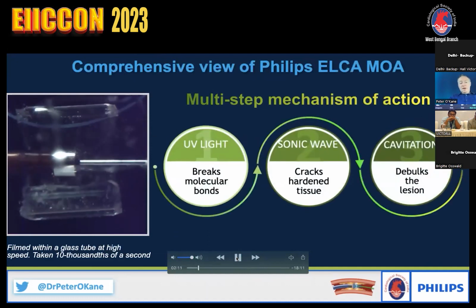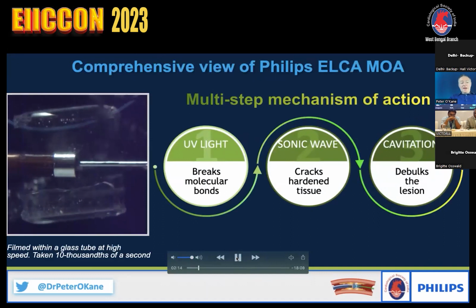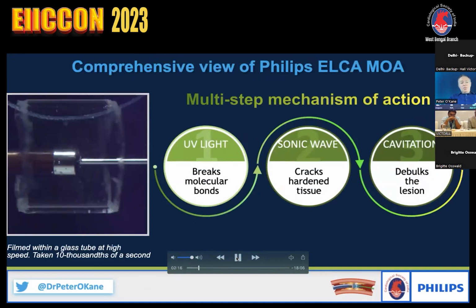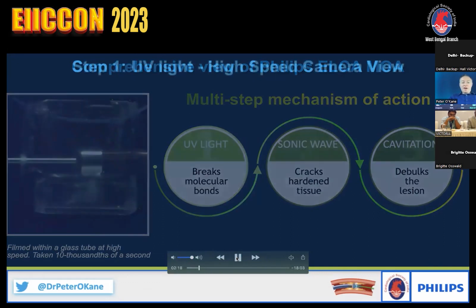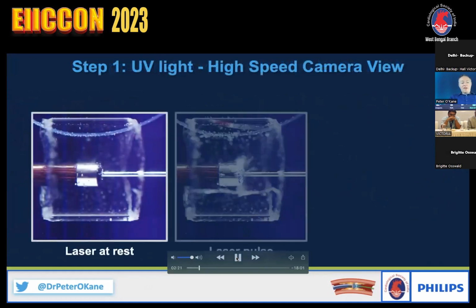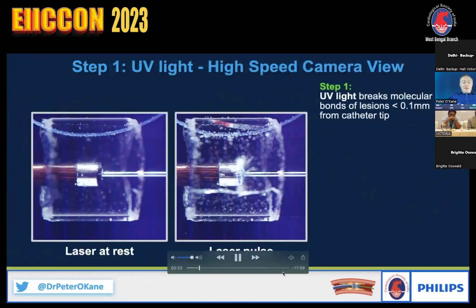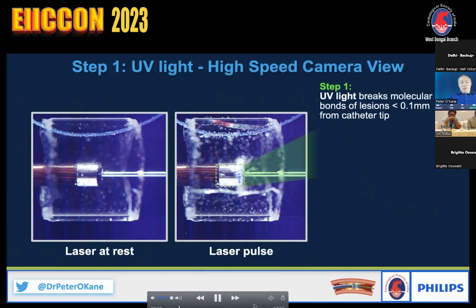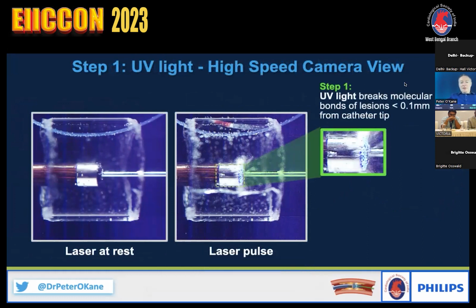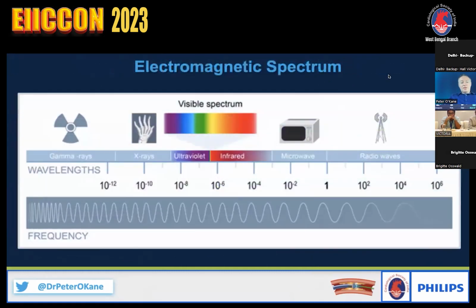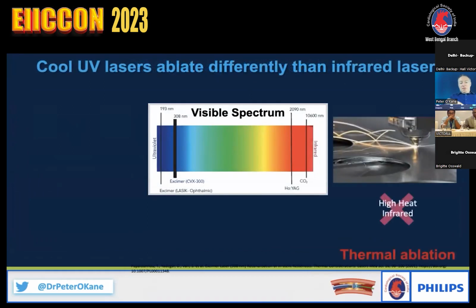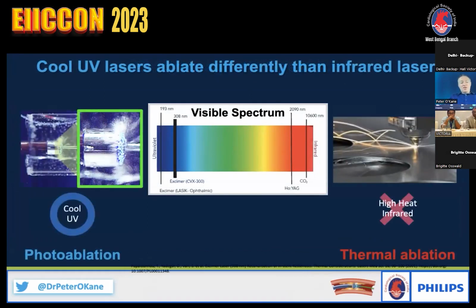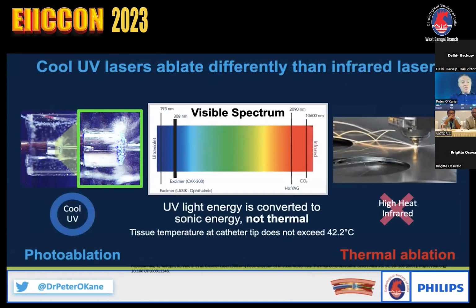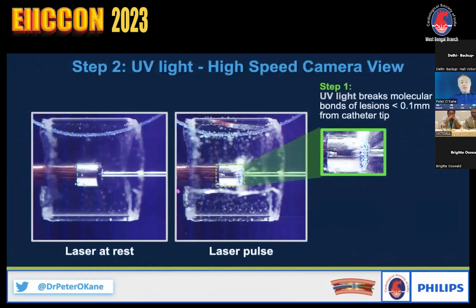How laser works, first thing is the light breaks up the molecular bonds, and this is quite important. We have to allow the light to penetrate into the tissue, so it's a very slow process when we're delivering laser energy. As the laser light goes into the tissue, it starts to crack these molecular bonds, and that weakens the tissue. Now, the laser itself is ultraviolet light, so it's a very shallow penetration depth, about 50 microns. So it's very small, and it doesn't damage the adjacent tissue. It just focuses really on the area of interest.